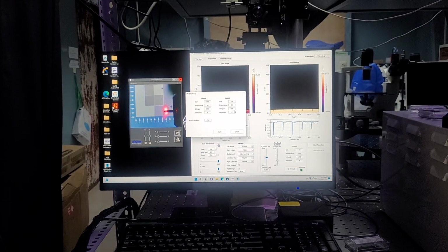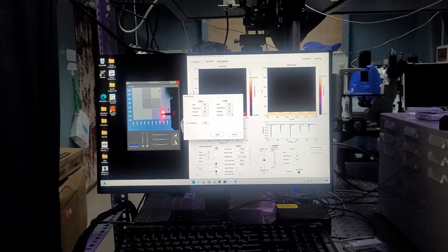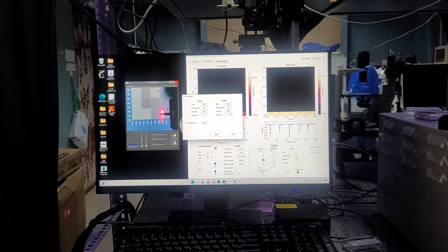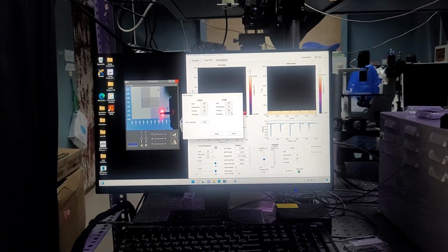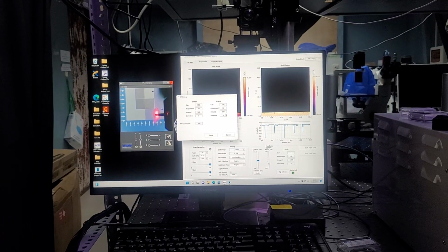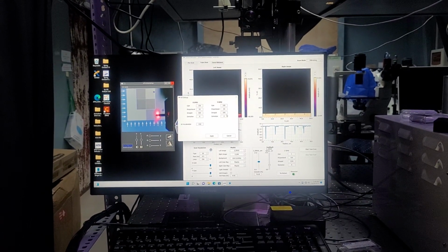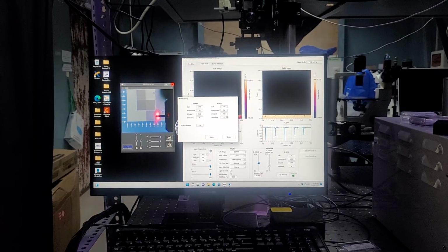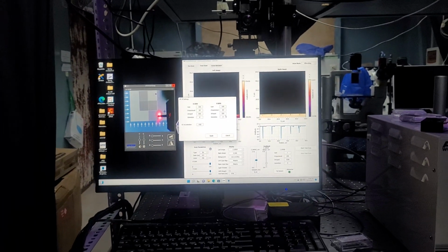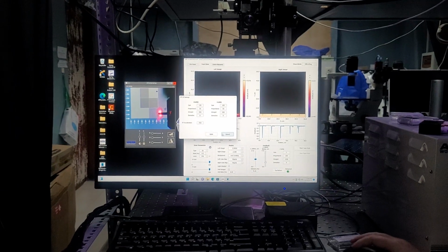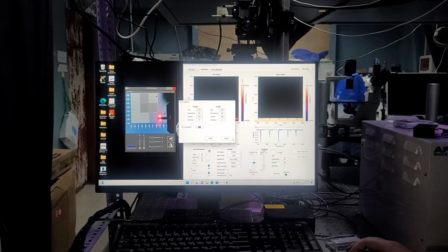Typically, if you're scanning 5 microns by 5 microns or bigger, you don't need to adjust these values. As soon as you start going below that 5 micron by 5 micron size and smaller, then these values will need to be adjusted, because then the noise that those strain gauges create will become noticeable and it will look fuzzy. Additionally, XY acceleration should stay at 450. Shouldn't need to adjust that.